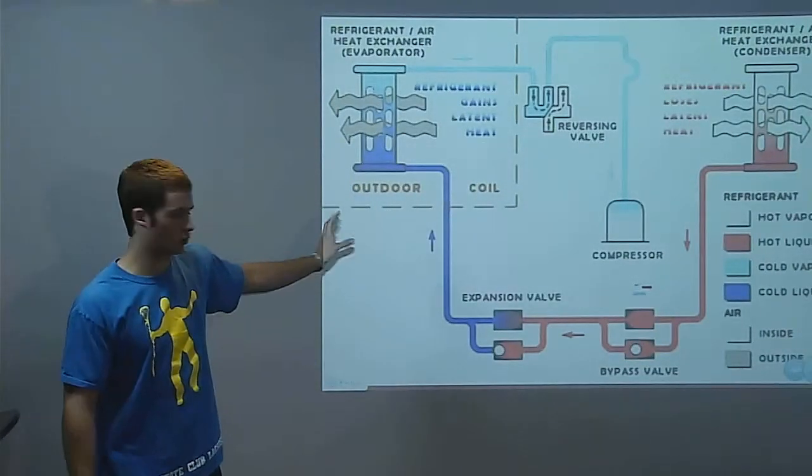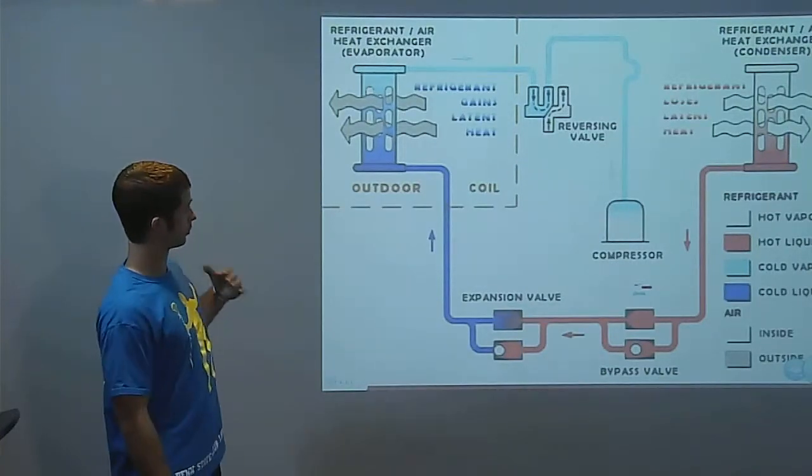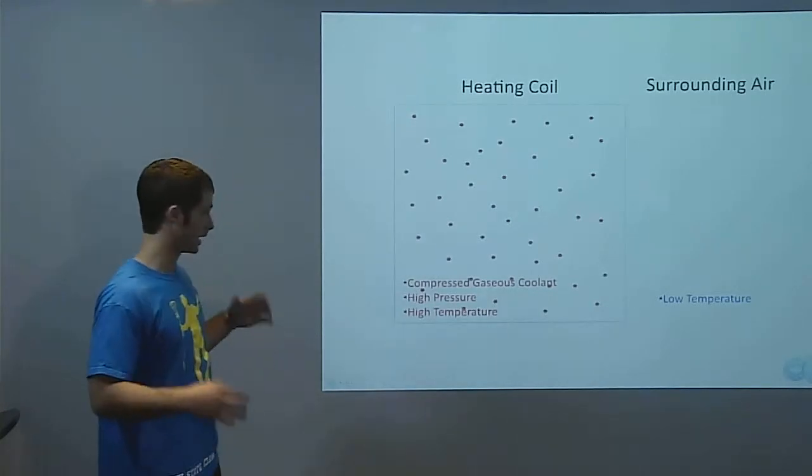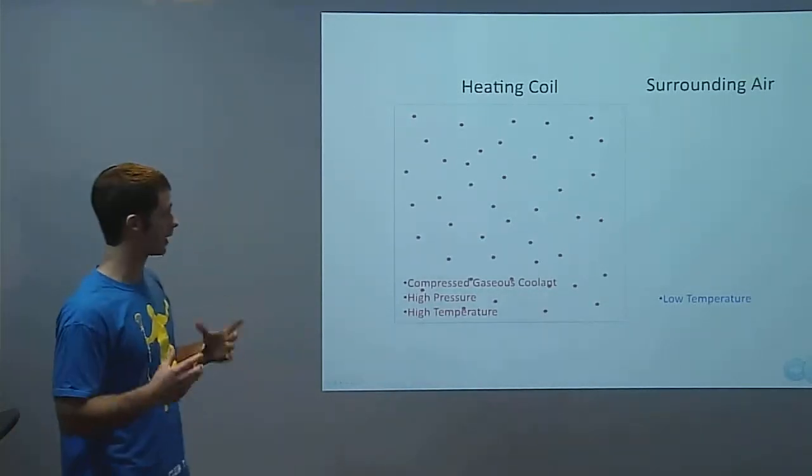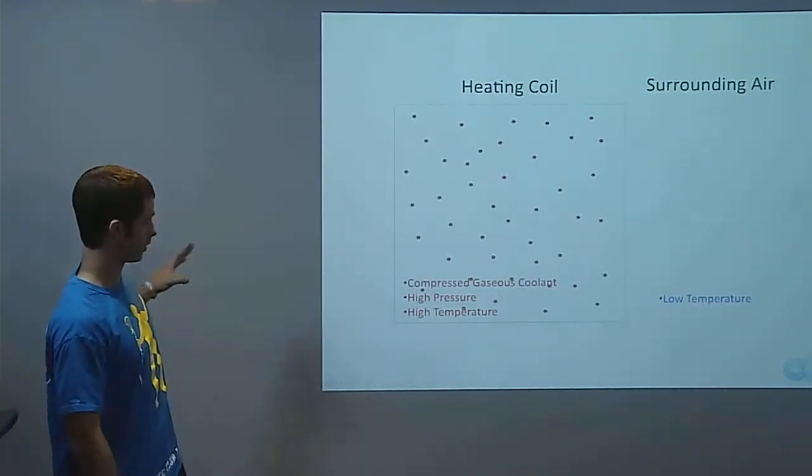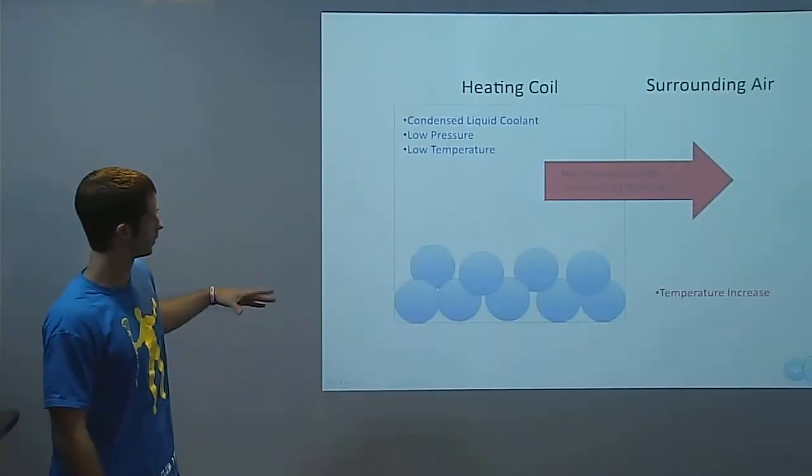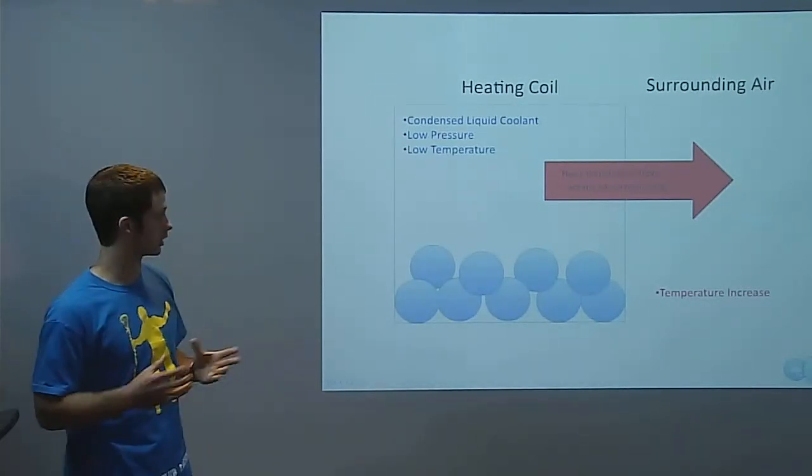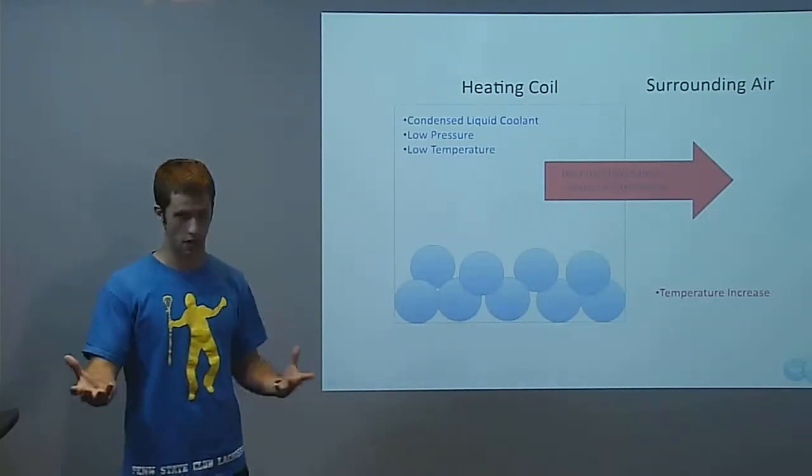In between that outdoor coil and the indoor coil, that gas will pass through a compressor, and what the compressor does is it takes that cool vapor and compresses it, giving it a higher pressure and a higher temperature. So now you have a very hot gaseous vapor flowing into the house, and it will flow through the heating coil. As it flows through the heating coil, that extra heat that's caused by the increased pressure and increased temperature will transfer from the coolant into the surroundings, being your house.